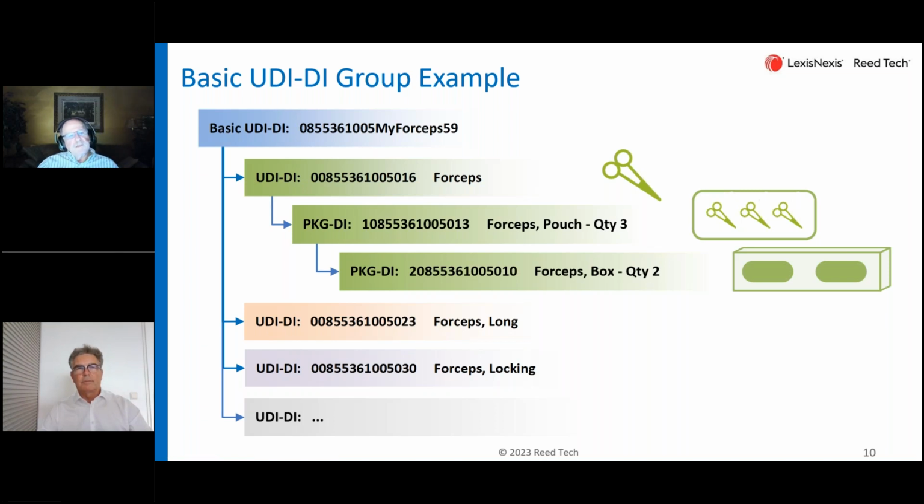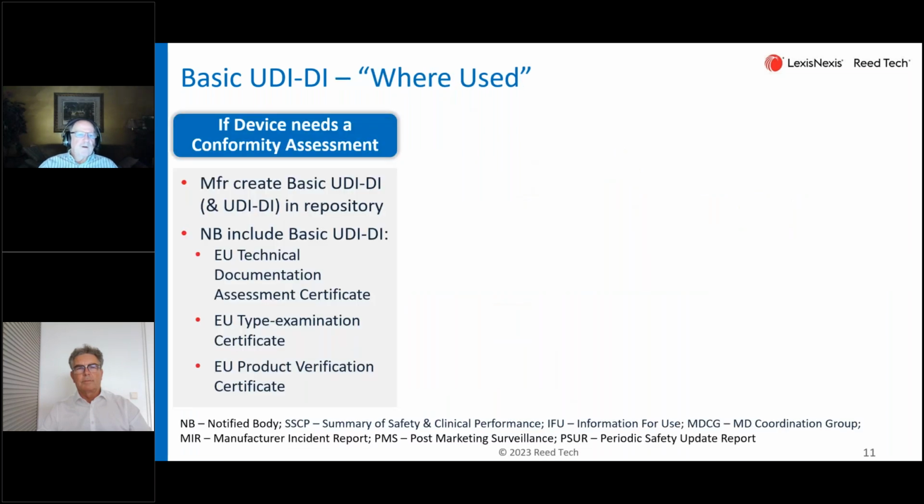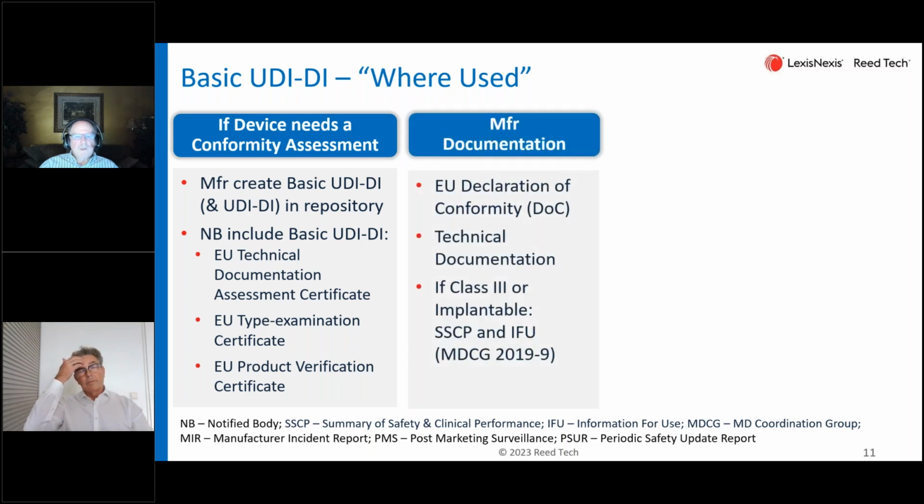And the last thing I'd like to touch on before we get into your live Q&A is where in the world this basic UDI is used. There's some early requirement: if you do need a conformity assessment and are working with a notified body, you'll have to create your basic UDI prior to actually engaging the notified body. So this is something that you should be working on as of now.